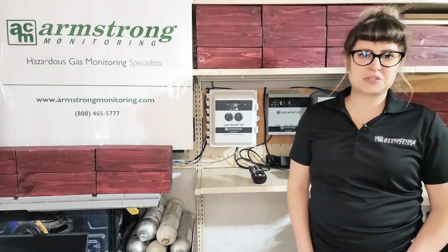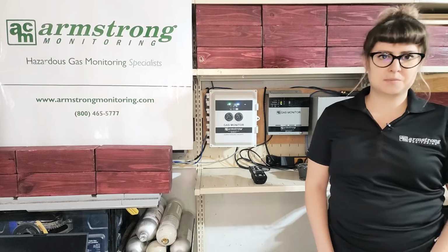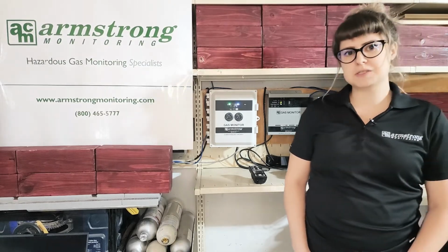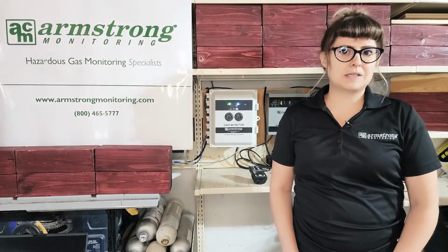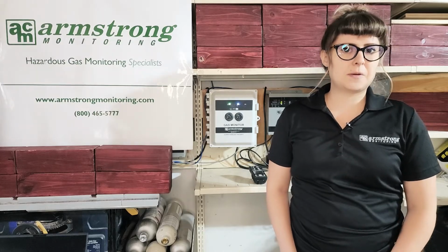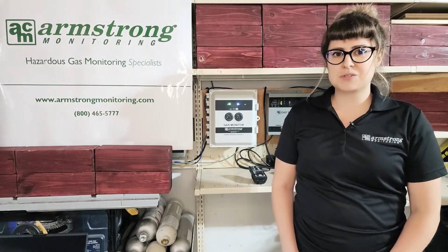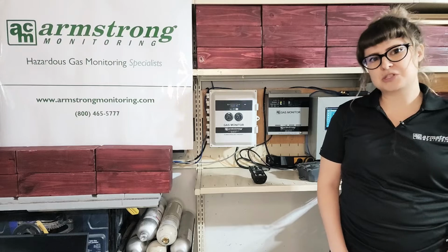So sensors tend to degrade through time, causing them to underreport gas concentrations, so they need to be recalibrated. We recommend to calibrate them once every 6 months. So let's go ahead and walk through the calibration using AdaptiCal.